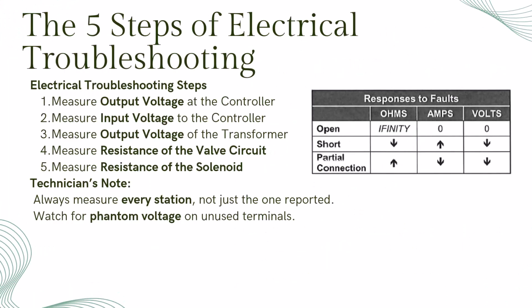Electrical troubleshooting follows a clear 5-step process that gives you the full picture of what's happening in the system. We start by checking voltage at the controller, then trace it back to the power source and transformer, before switching to resistance readings on the valve circuit and solenoid. This sequence ensures that we identify not just where the problem appears, but why it exists. And always remember, test every station, not only the one reported. A problem in one zone can often point to something larger, like a common wire issue or a phantom voltage reading. The chart on the slide shows the relationship of how each responds to faults.